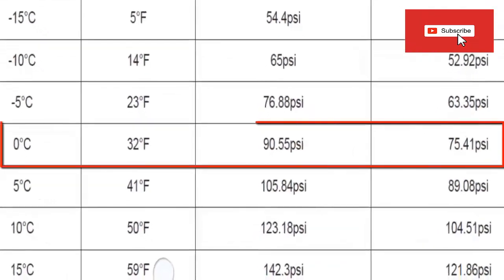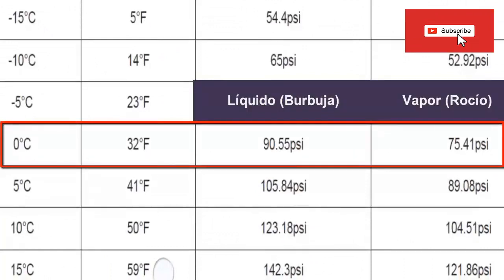On the screen we have other pressure values that are usually used with R449A. Since R449A is used as a replacement for R404A, in medium temperature applications we are going to focus on these pressure values. For example, to achieve a temperature at the inlet of the evaporator of 0 degrees Celsius, an absolute pressure of 90.55 psi must be present at low side. On the other hand, if you require 0 degrees at the evaporator outlet, then you must work with an absolute low pressure of 75.41 psi. Remember these table values are absolute — subtract your local atmospheric pressure; you can use 14.7 psi for a quick calculation.